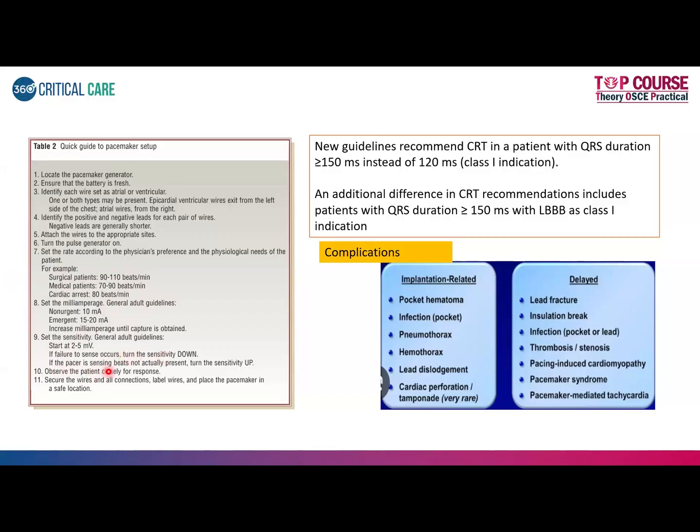If the pacer is sensing beats which are not actually present, then turn the sensitivity up. So this is an important point that one needs to know to prevent undersensing and oversensing. All right, see for the patient responses and keep continuously securing the wires and all the connections.